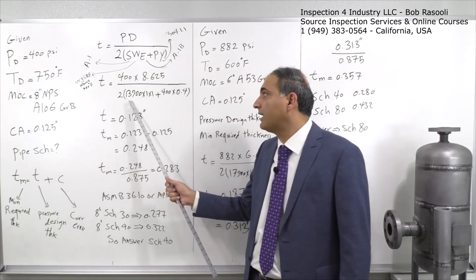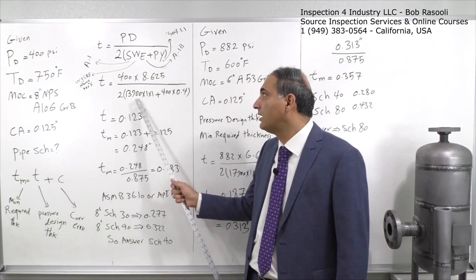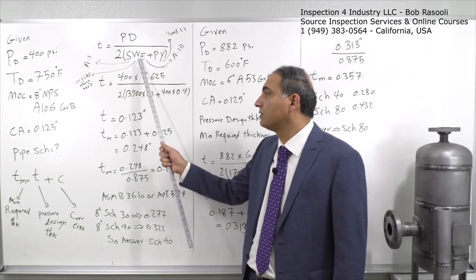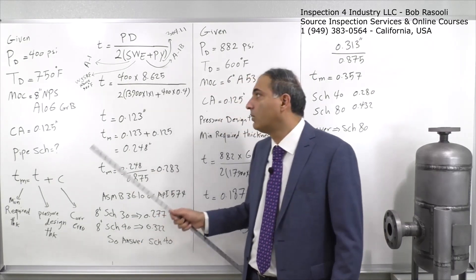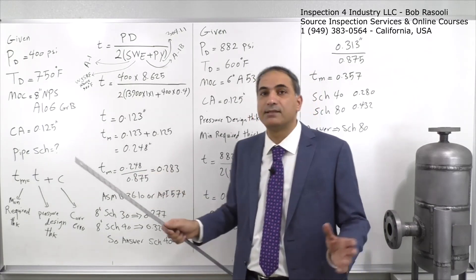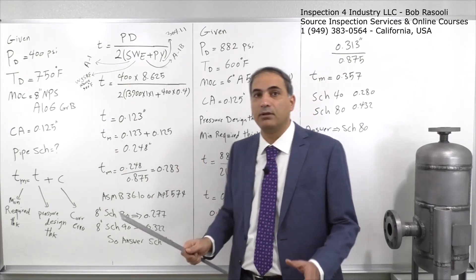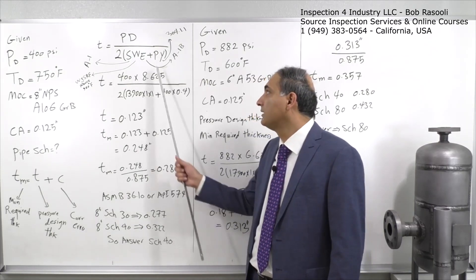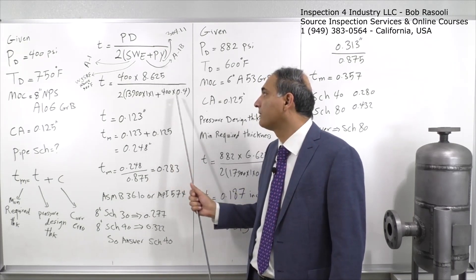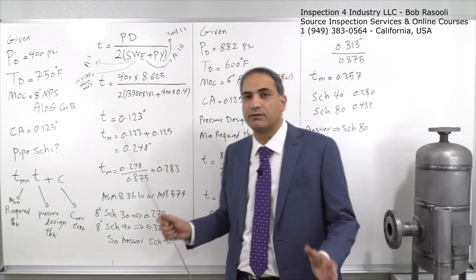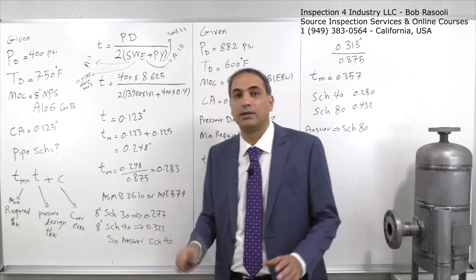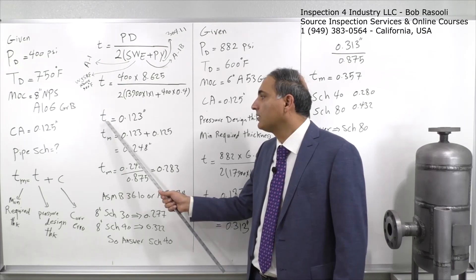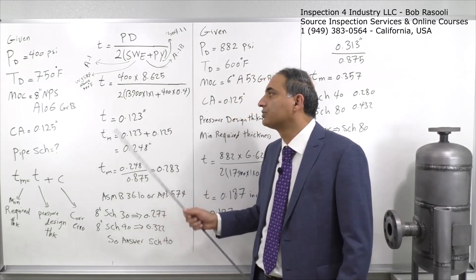Our W equals 1 since the temperature is below 900°F. The joint quality factor E also equals 1 because A106 Grade B is a seamless pipe. The Y coefficient, read from the table for our design temperature, is 0.4 — the most common value. Plugging all values into the formula, our pressure design thickness T comes out to 0.123 inches.